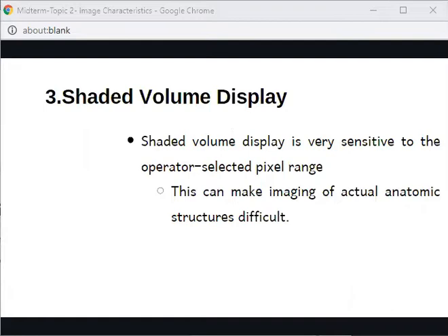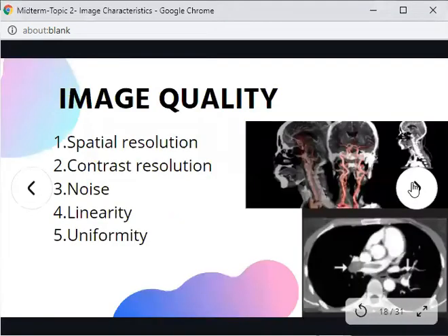The shaded volume display (SVD) is very sensitive to the operator-selected pixel range — the operator sets the pixel range that SVD uses to detect and select pixels. This can make imaging of actual anatomic structures difficult, which is its main disadvantage.